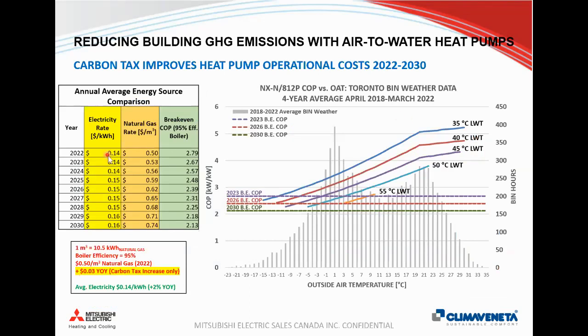So just forecasting this using today's rate of electricity of about 14 cents, I'm applying here 2% inflation year over year for electricity prices. Natural gas: 2022 at 50 cents, 2023 at 53 cents, and then adding that 3 cents year over year just for the carbon tax portion. And this chart here is showing us the COP curves that we were looking at before, but we've also put here a horizontal line showing the break-even COP. So if we're designing, for example, a system with a 50-degree supply temperature, based off these rates today, that would be economical. It would save you money whenever the heat pump curve is above this line. So in this example, at 50 degrees C, this is economical. It's actually saving you money down to about -3.